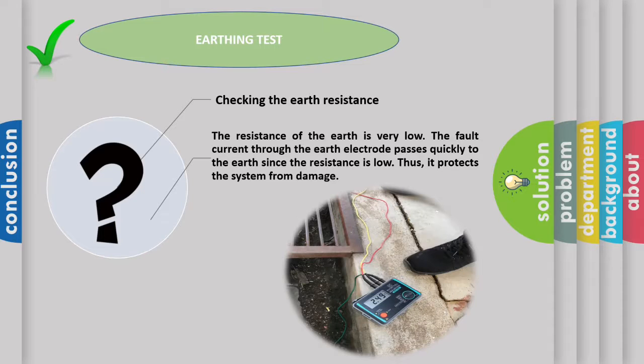Here are some results of the earth test. The earth tester tools show the result of 2.49 ohm, where the value of the earth resistance is in good condition because it below than 3 ohm.